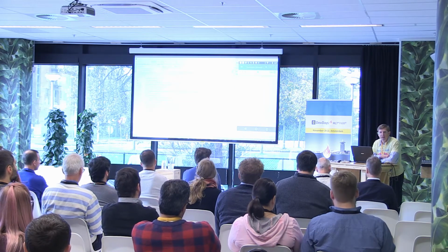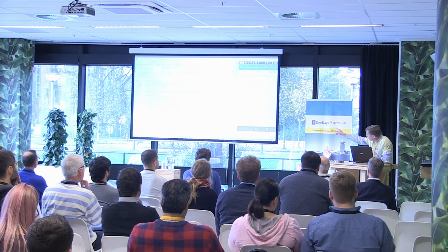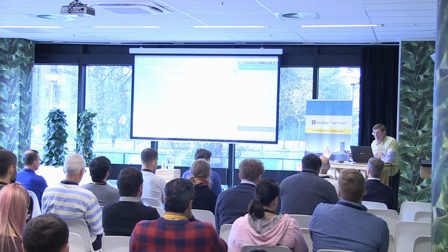All right. So what the PHD implementation guide profile does, it explains how to take PHD data, and I've got a bunch of devices up here that I'll have to play with. To take that data, a gateway will communicate with it. In this case, it's on this phone, and you can see it over here on the side. I've got a Droid screen showing it. You take a measurement, the phone decodes it, the gateway then converts that data into FHIR, following the PHD implementation guide, and uploads it to a FHIR server. And that's basically where it stops.